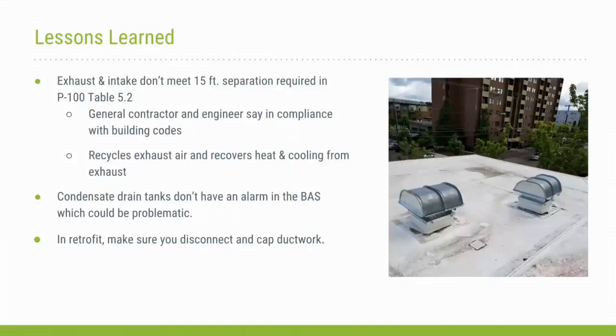And incidentally, there are 2 penetrations here, exhaust, outside air. And then for the other Losnay, there's another exhaust and outside air. So there's 4 penetrations for just this little 5,000 square foot area. So in terms of your penetrations to the roof and mitigating water damage in the future, this is not the best solution. But they weren't far enough apart. We had a debate as far as whether they needed any separation at all. If you look in the DOAS ASHRAE book, it talks about a minimum of 10 feet, which is the mechanical code requirement. They argued it wasn't an exhaust, but I don't agree with that.